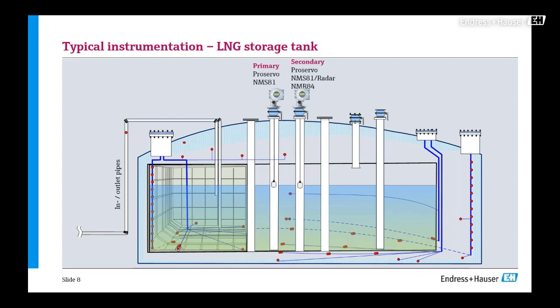Here we are talking about the primary and secondary gauge. For the primary gauge, we often recommend using our servo gauge, and for the secondary you can also use a servo gauge. But if you need a diverse technology different from the primary, we can also offer radar technology. Primary, we always recommend a servo gauge. The reason is, later I will show some unique characteristics and advantages of the servo gauge, one being accuracy. Today, the accuracy of the servo gauge is the highest with regard to level measurement. That is one advantage.